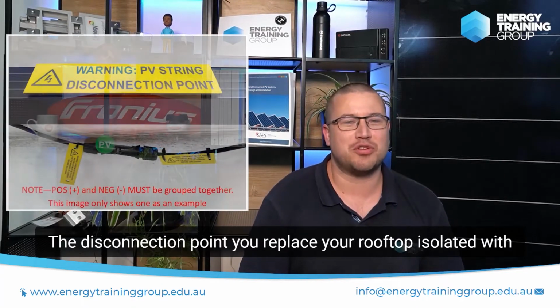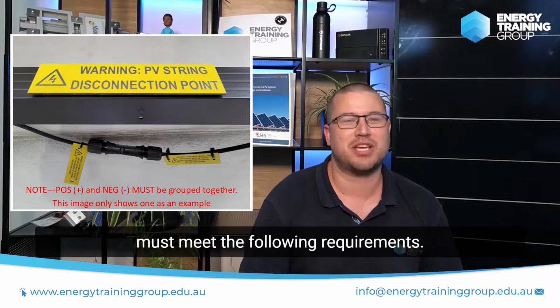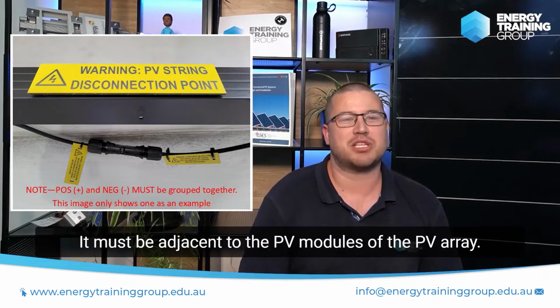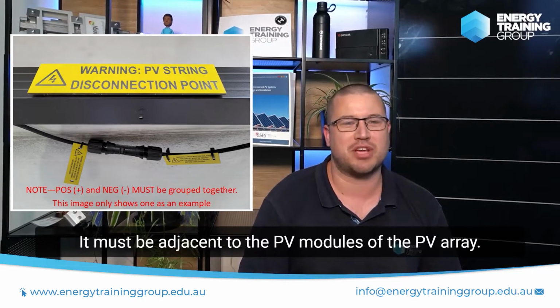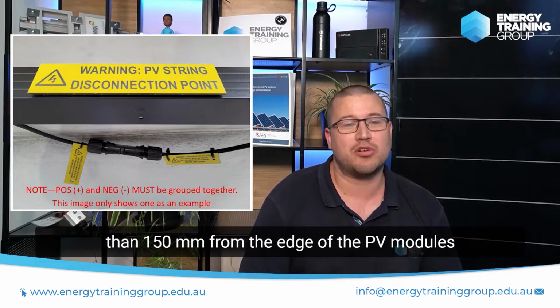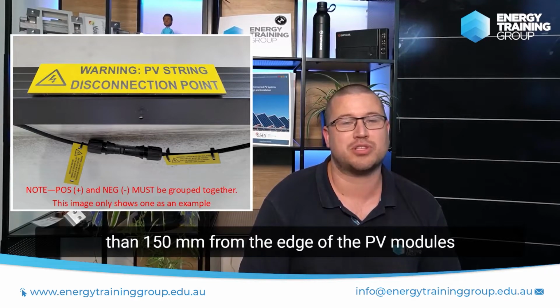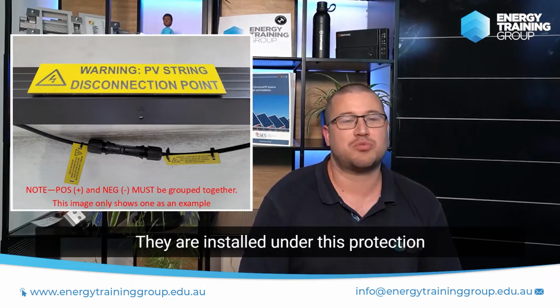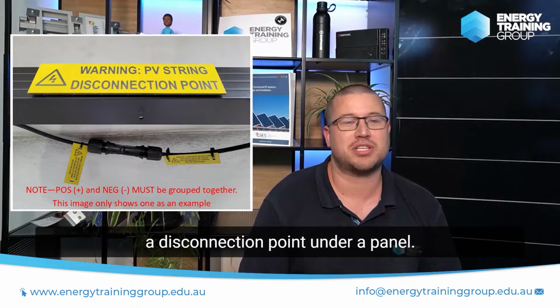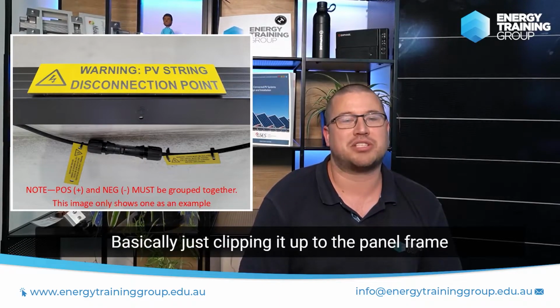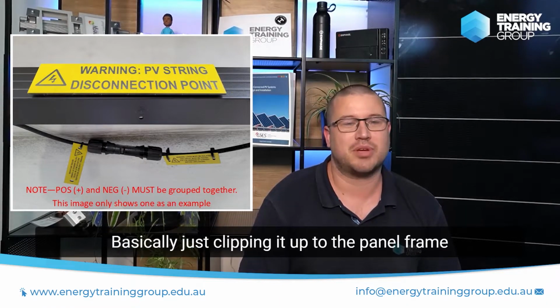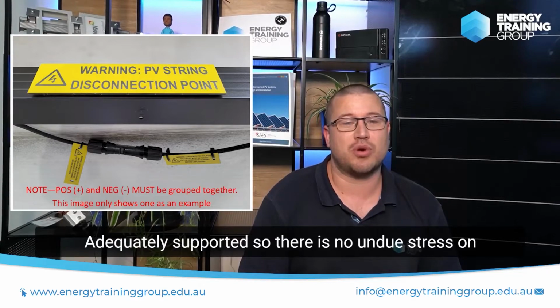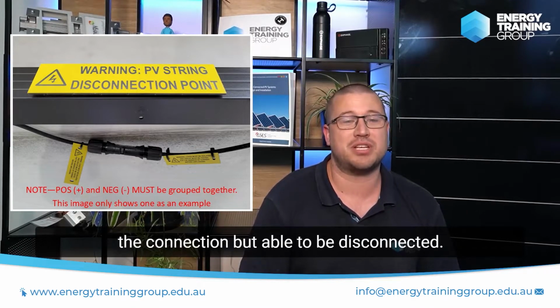The disconnection point you replace your rooftop isolator with must meet the following requirements. It must be adjacent to the PV modules of the PV array. It must be readily available. It must be protected against weather and water and no more than 150mm from the edge of the PV modules that they are installed under. This protection requirement can be satisfied by installing the disconnection point under a panel, basically just clipping it up to the panel frame. Adequately supported so there is no undue stress on the connection, but able to be disconnected.